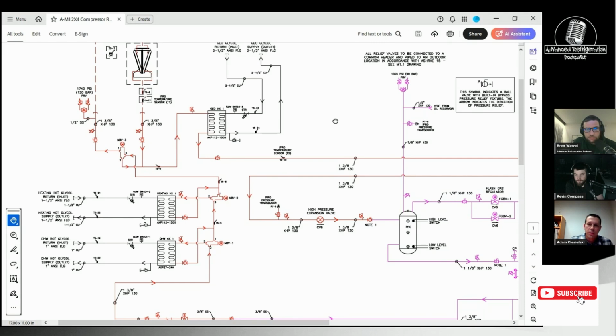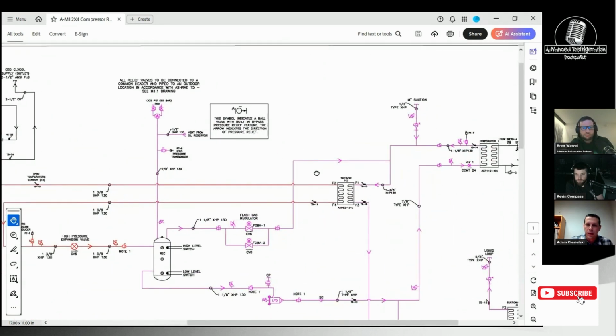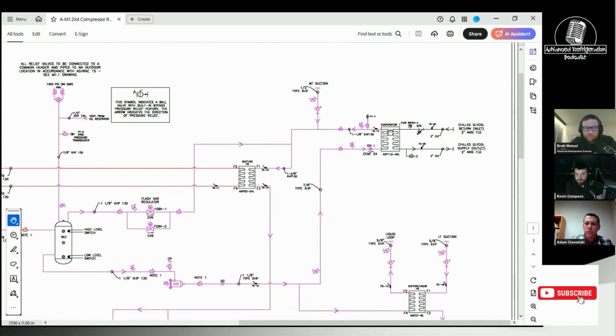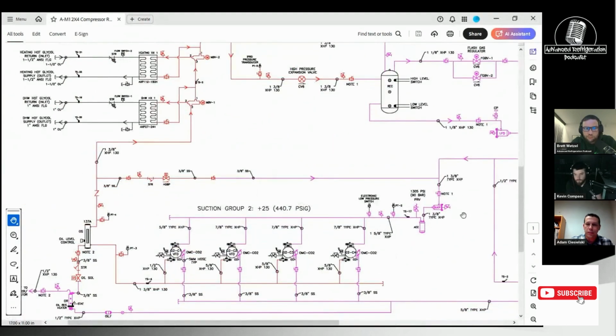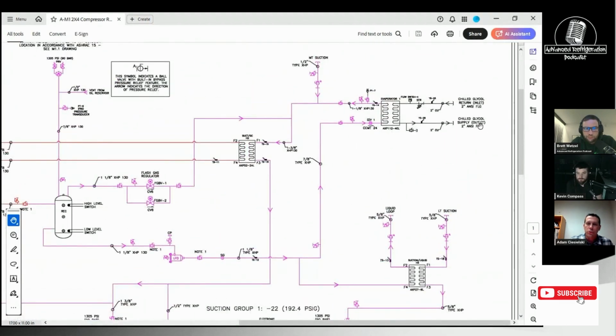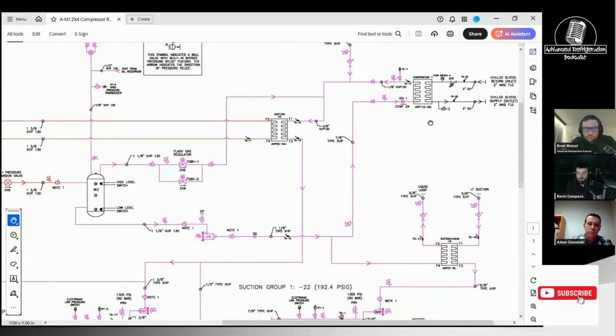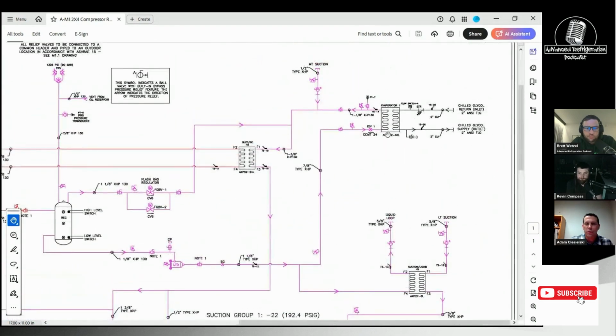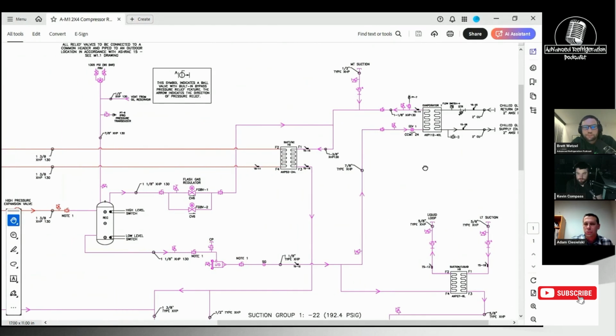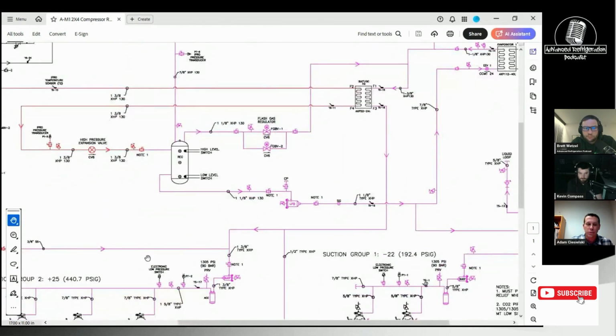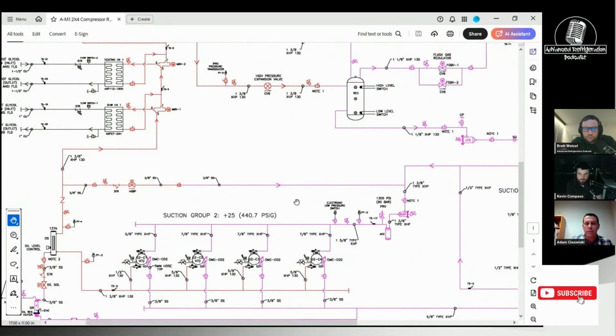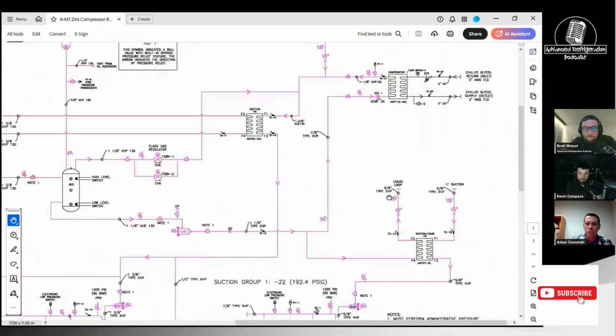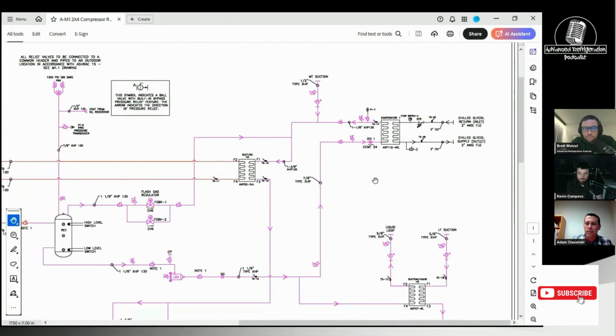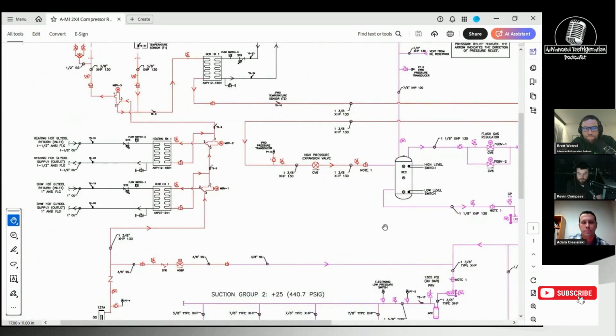You potentially could do that, but the problem is like I mentioned, we do have an evaporator, a glycol. So if we need to, in order to get more heat, we got to produce more load. We got to get more compressors running, right? So if I can't dump more load into this glycol loop, then I can't produce any refrigeration effect, and I got no compressor. So if I were to float that up, then essentially I'm reducing the load on the glycol side. So it wouldn't help. What we did a little bit is we actually reduced the suction pressure set point, made the compressors run a little bit harder. We reduced the set point on the glycol loop, and it did give us a little bit more heat output.